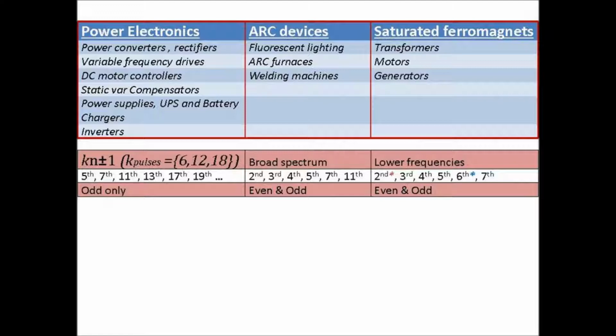For a 12 pulse, you have very small amounts of 5th and 7th. It'd be diminished by over 90%. But you'll still have the 11th and 13th, and multiples of 12, so you'll have the 23rd and 25th and all the way up along. And for the 18 pulse, you'll have 17 and 19, but you still have small amounts of 5th and 7th and 11th and 13th as well.